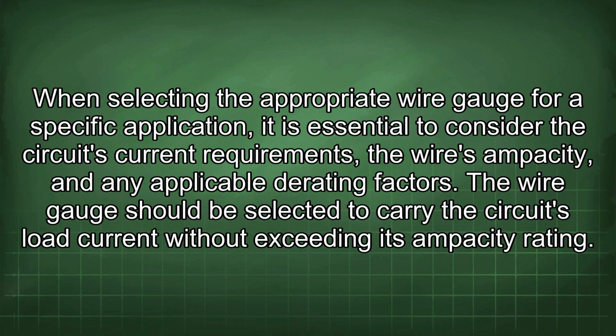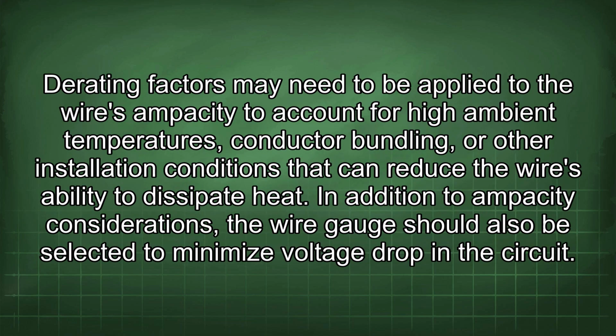When selecting the appropriate wire gauge for a specific application, it is essential to consider the circuit's current requirements, the wire's ampacity, and any applicable derating factors. The wire gauge should be selected to carry the circuit's load current without exceeding its ampacity rating. Derating factors may need to be applied to the wire's ampacity to account for high ambient temperatures, conductor bundling, or other installation conditions that can reduce the wire's ability to dissipate heat.